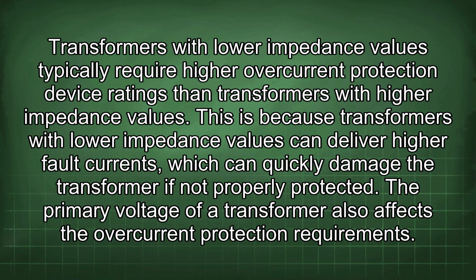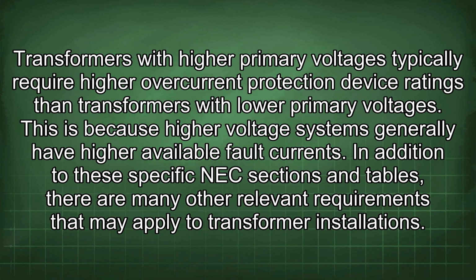not properly protected. The primary voltage of a transformer also affects the overcurrent protection requirements. Transformers with higher primary voltages typically require higher overcurrent protection device ratings than transformers with lower primary voltages. This is because higher voltage systems generally have higher available fault currents.